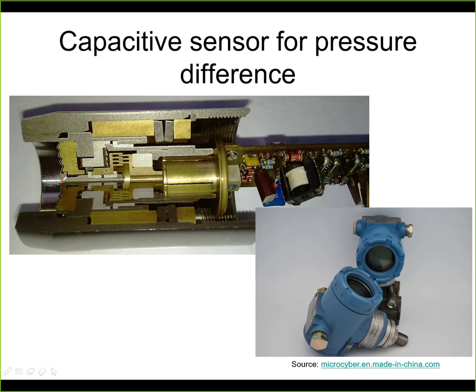Here we can see the diaphragm. So this is changing its shape when we apply the pressure. This is the rod that moves left and right as the diaphragm is changing. And here this is the set of the electrodes. So you can see that this is the fixed electrode fixed to the frame in here, and this is the movable electrode, and this moves left and right. So as you apply pressure on the diaphragm, now this moves to the left, it moves more into the capacitor, and hence we have an increase in capacity.